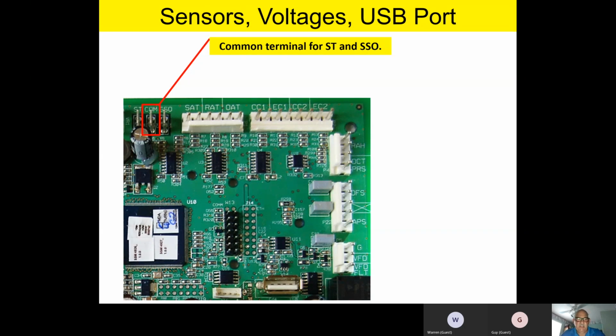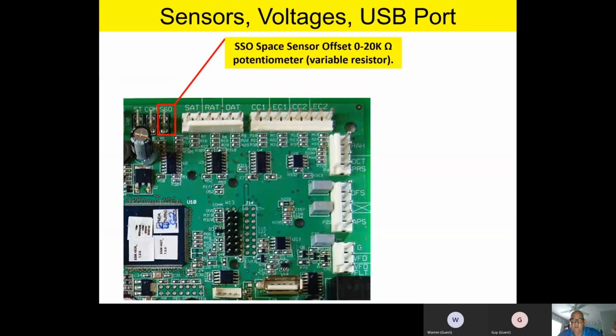Okay, well, right next to ST and common, there's another little input. It's called a space sensor offset, and this is a variable resistor or a potentiometer, 0 to 20,000 ohms. What that's for is, if you've got like a building management system on the board, you can use that SSO offset to help offset any temperature differentials from the sensor where it's sitting in the space. Typically, this is not used with a conventional thermostat, but just for a point of education, it is a space sensor offset that you can put in there with a variable resistor on a building management system.